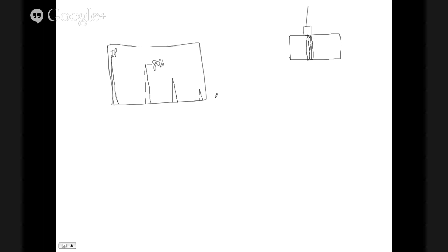So what they mean by this is that if it's linear, these are echoes. This is my first echo, this is my second echo, this is my third echo of the same back wall. So if this one, let's say, is a 40, this one should be at 20. And what they were talking about is that if you were to change your amplitude, your gain, or your volume control, let's say you lowered it by 6. If you lowered the volume by 6, these amplitudes are going to go down.